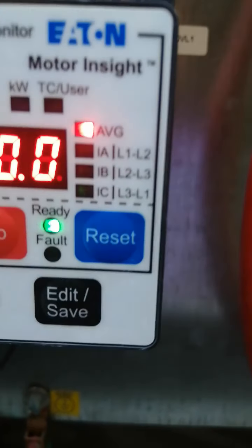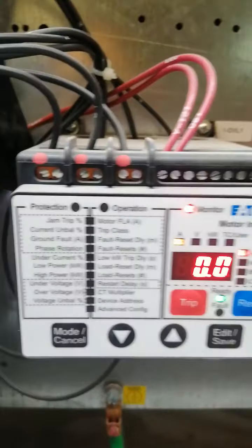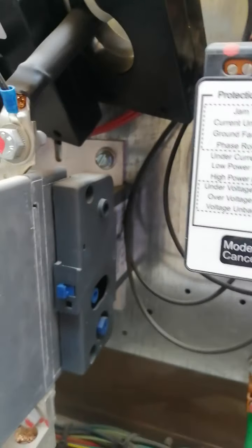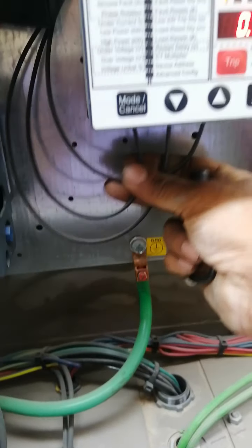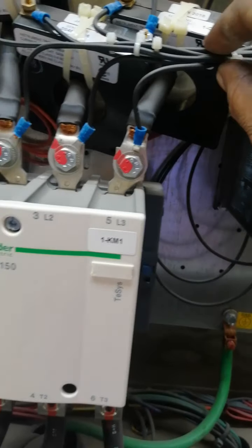Okay, that is now ready. Okay, so these 3 are CT, these are going to the motor protector. Check, their CT is going to the motor protector. Okay, so what is our control voltage? In this control voltage, there is a three phase, and this is for relay NO point, NC point. Okay, that is going to start for this control relay, and these three are coming from CT. It is coming from CT one side, and the second side is also going to CT. Okay, now I will close this door and show you the mechanical part of this. That is this diagram, control diagram, all control and power diagram. Okay, now I will close this door.